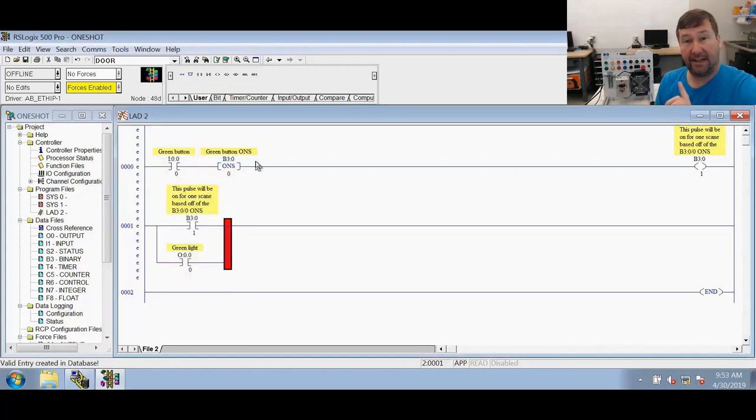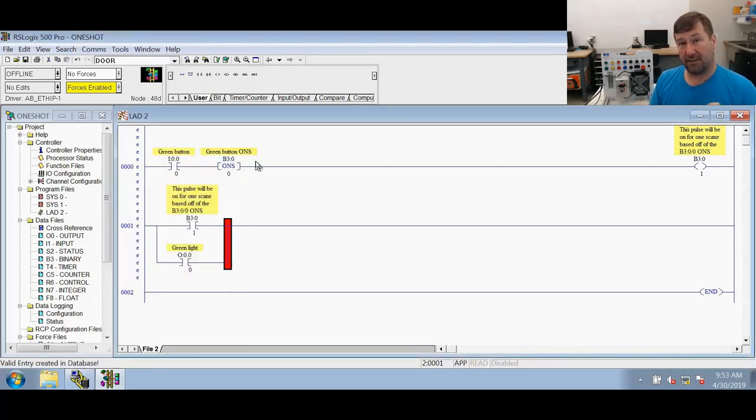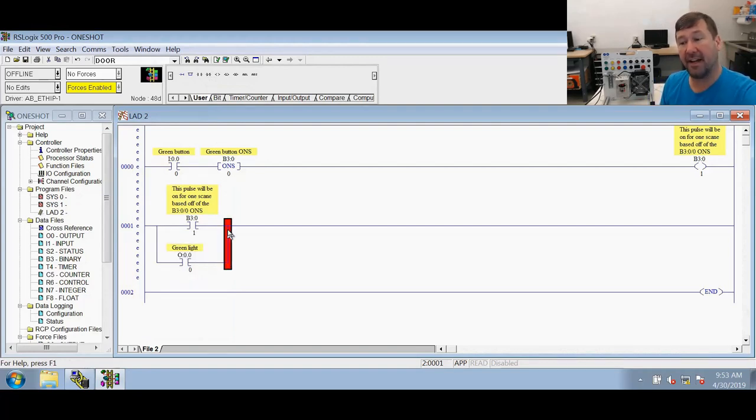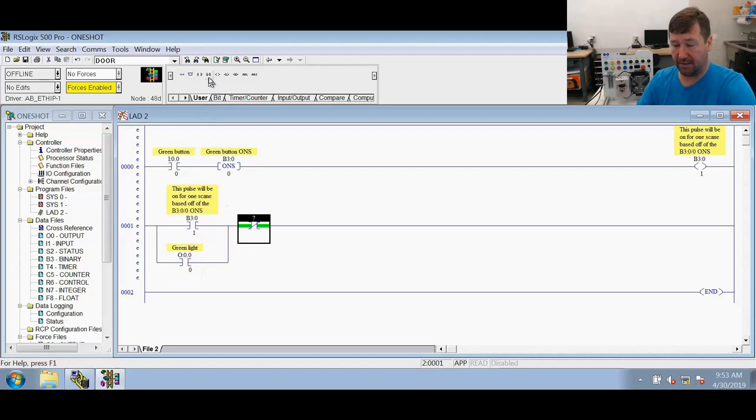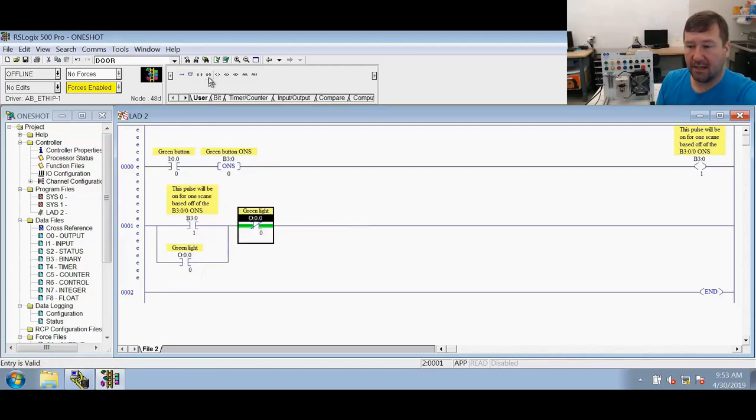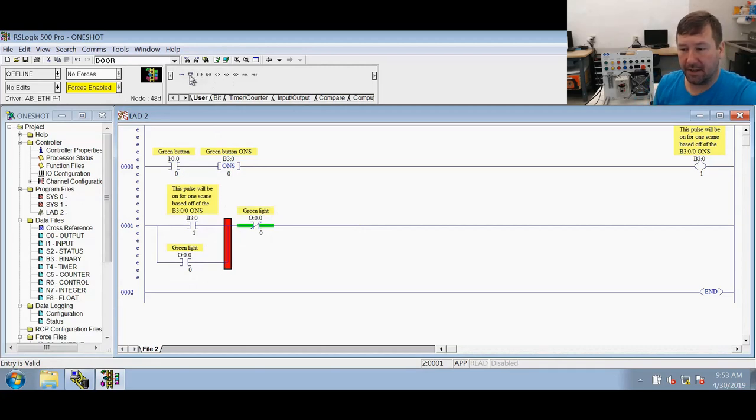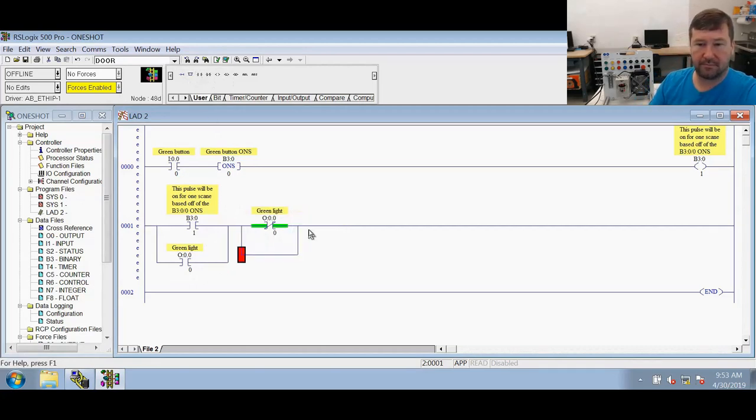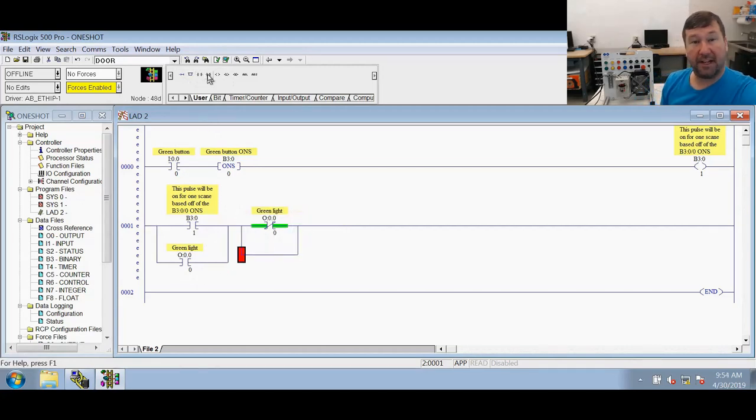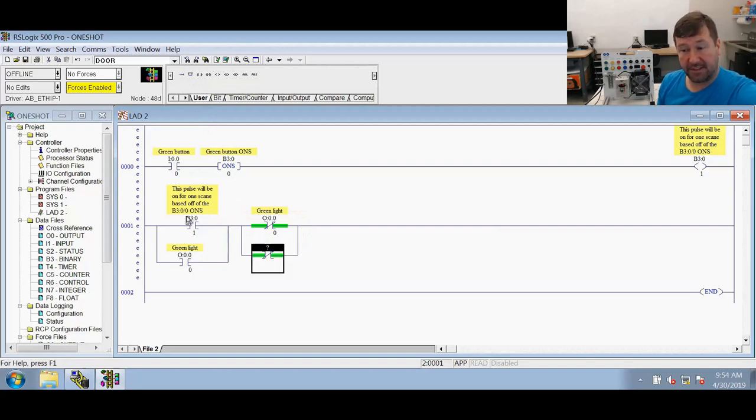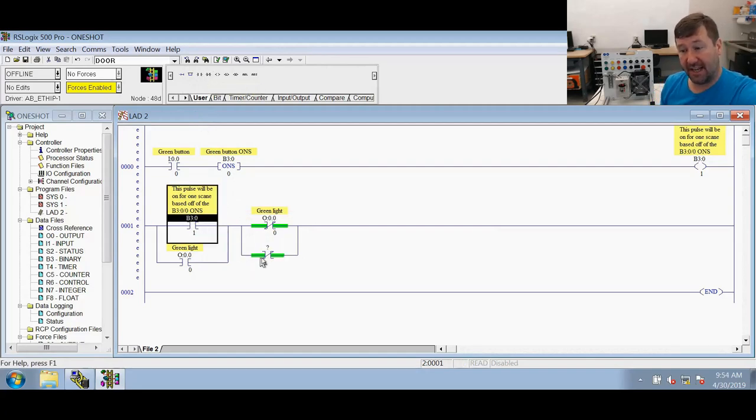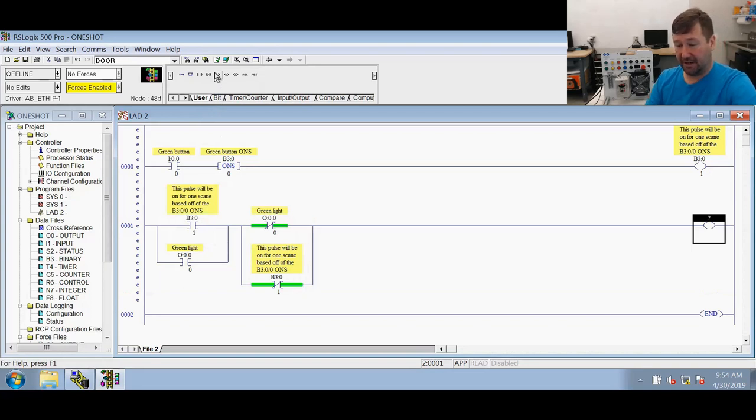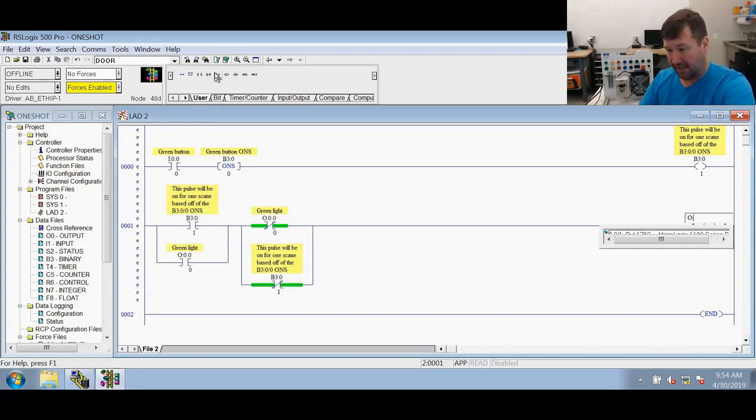Now it's going to get a little tricky understanding. But where we just did an XIC of this green light, now we're going to do an XIO of this green light. So that's O colon zero backslash zero. And we're going to put another branch around that one. Now we're going to put an XIO of the same bit that we just had here. And then this is going to be an OTE to the green light.